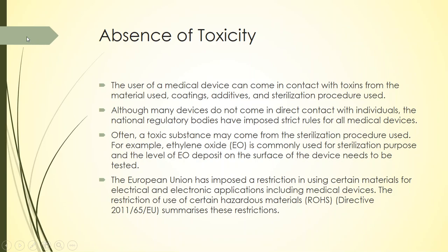So for sterilization, often you use ethylene oxide to sterilize the surface of a material, and this results in deposition of ethylene oxide particle on the surface. So the amount of ethylene oxide that is deposited on the surface needs to be tested, because if it is alarmingly high, then that can cause harm to the person handling the device.